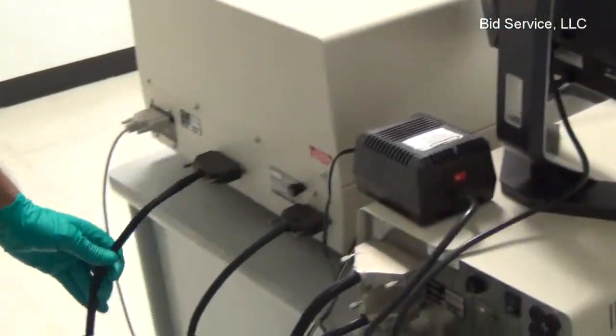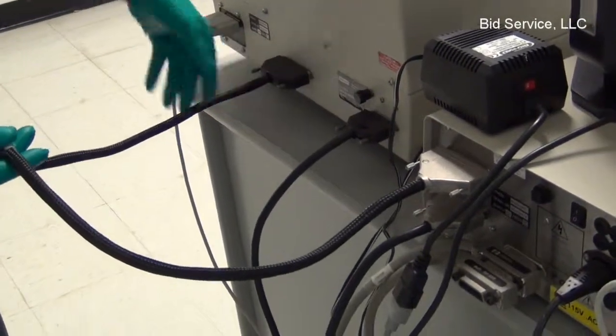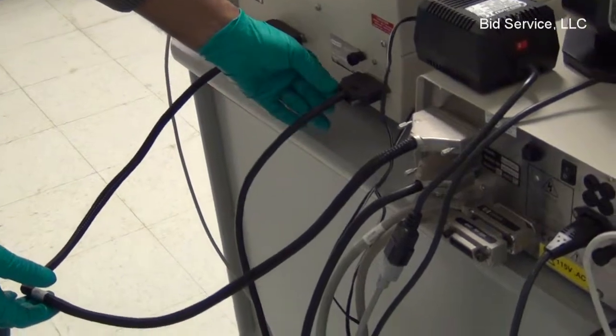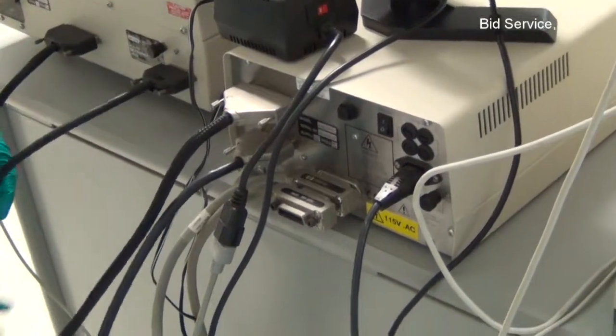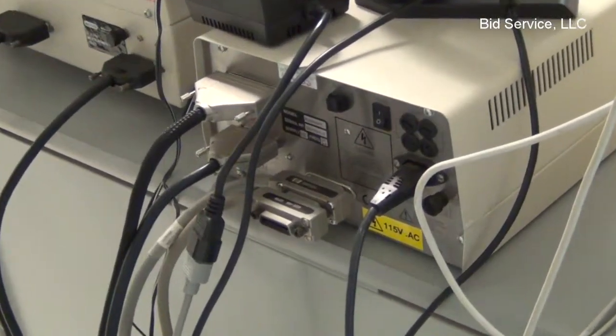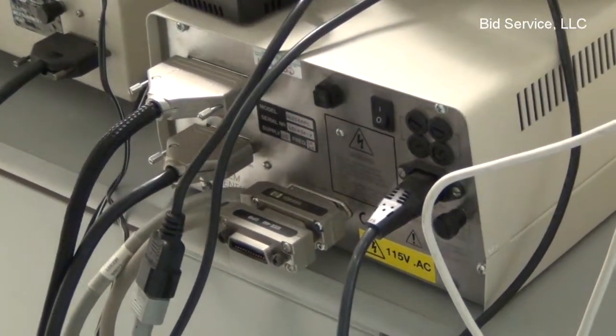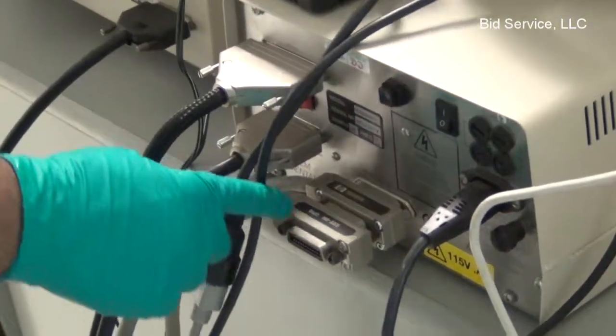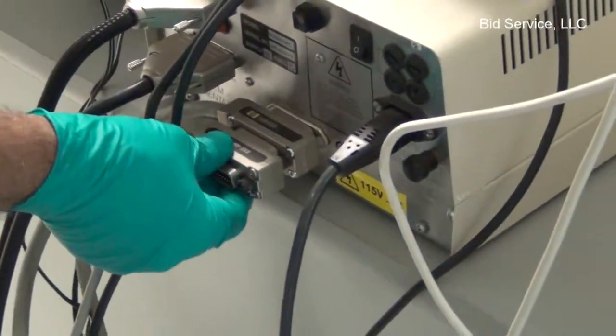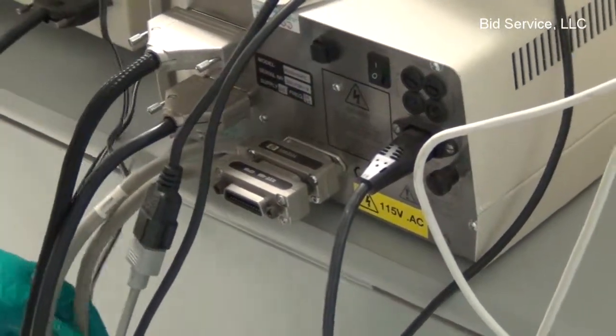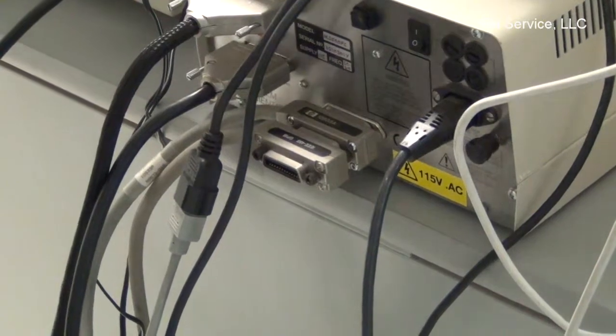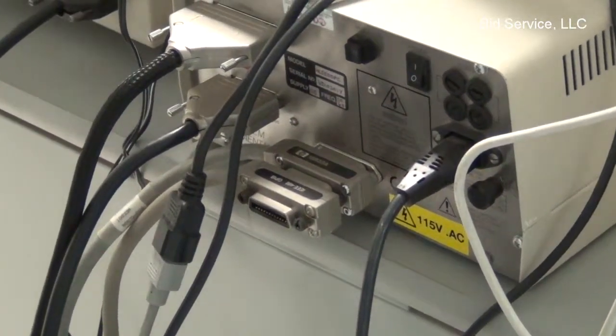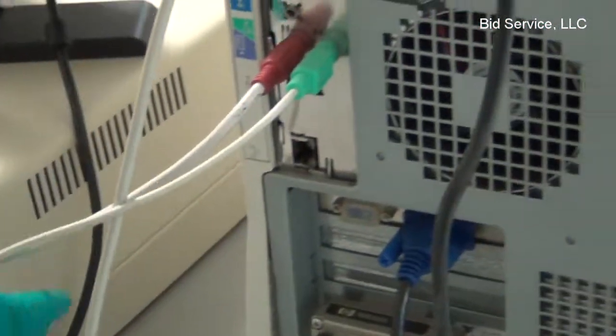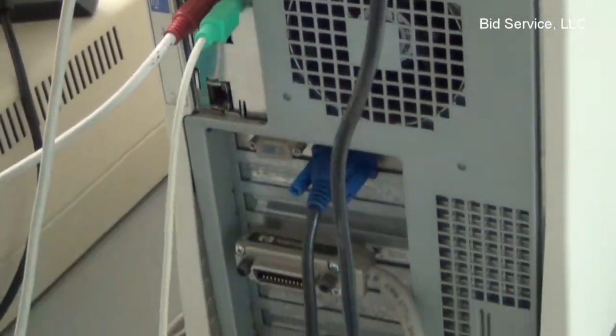And there are two more interface connectors. This one is carrying the signals, the six connections. And this one is the magnet motor driver connection cable from the HL5500 system. And the PC talks to the system via these IEEE 488 GPIB interface cables. There's an extra connector available in case one more unit is to be hooked up. And the regular mouse and keyboard cable connections and the VGA graphics connector. This is the power supply for the microscope illuminator.